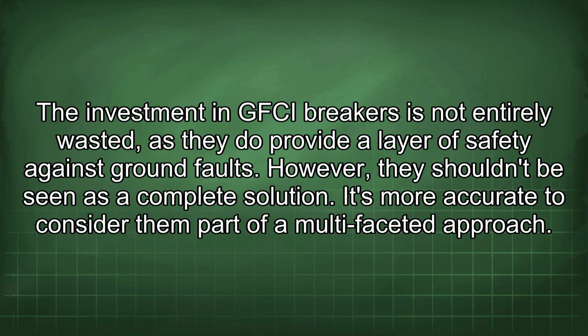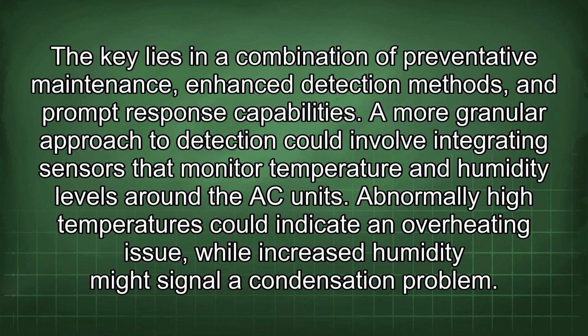The investment in GFCI breakers is not entirely wasted, as they do provide a layer of safety against ground faults. However, they shouldn't be seen as a complete solution. It's more accurate to consider them part of a multifaceted approach. The key lies in a combination of preventative maintenance, enhanced detection methods, and prompt response capabilities.